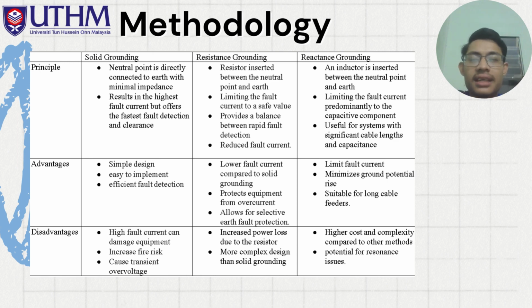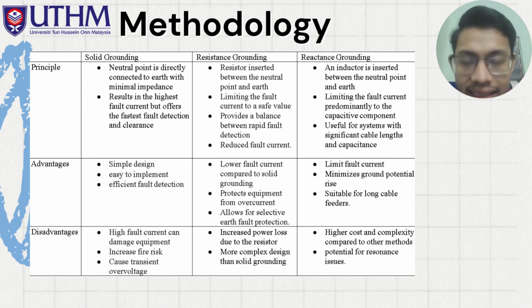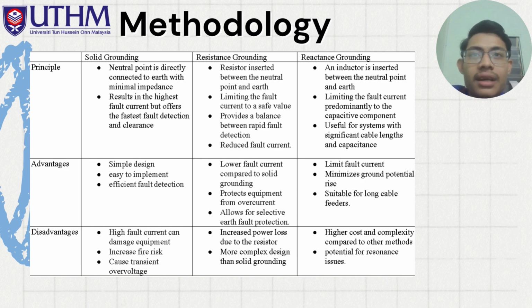And the second neutral grounding is resistance grounding. A resistor is inserted between the neutral point and earth, limiting the fault current to a safe value, and provides a balance between rapid fault detection and reduced fault current. The advantages are lower fault current compared to solid grounding, protection of equipment from overcurrent, and selective earth fault protection. The disadvantages are increased power loss due to the resistor and a more complex design than solid grounding.